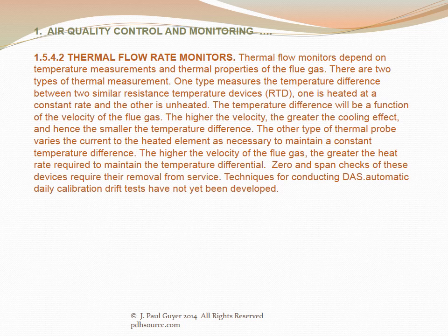Thermal flow monitors depend on temperature measurements and thermal properties of the flue gas. One type measures the temperature difference between two similar resistance temperature devices, abbreviated RTD — one is heated at a constant rate and the other is unheated. The temperature difference is a function of flue gas velocity; the higher the velocity, the greater the cooling effect and hence the smaller the temperature difference. The other type varies the current to the heated element to maintain a constant temperature difference. Zero and span checks of these devices require their removal from service. Techniques for conducting DAS automatic daily calibration drift tests have not yet been developed.